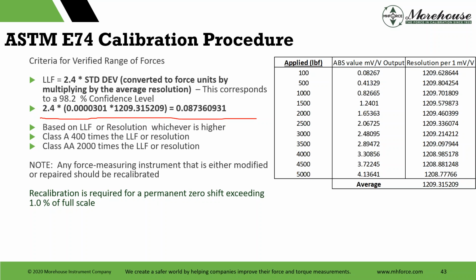And we reported it on our cert as 0.0874. It's based on the LLF or resolution, whichever is higher. The class A is 400 times the LLF or resolution, class AA 2000 times. Any force measuring instrument that is either modified or repaired should be recalibrated. That's per the standard. And recalibration is required for a permanent zero shift exceeding 1% of full scale.